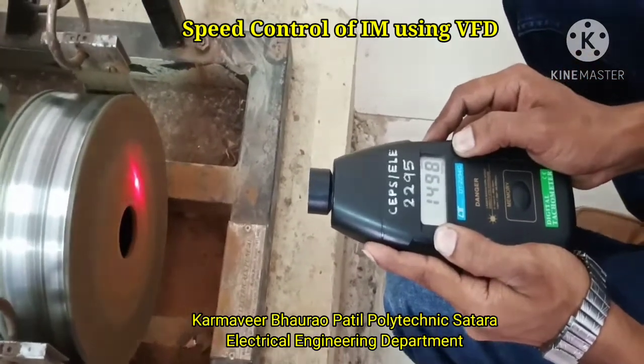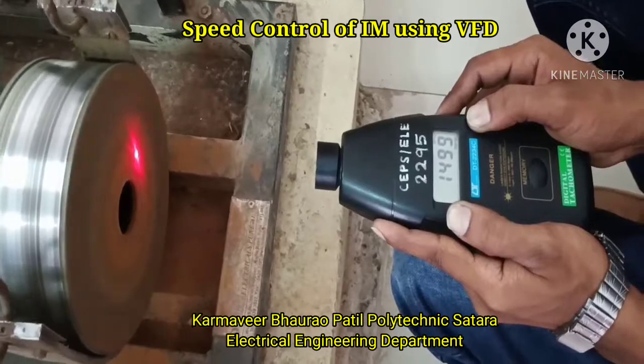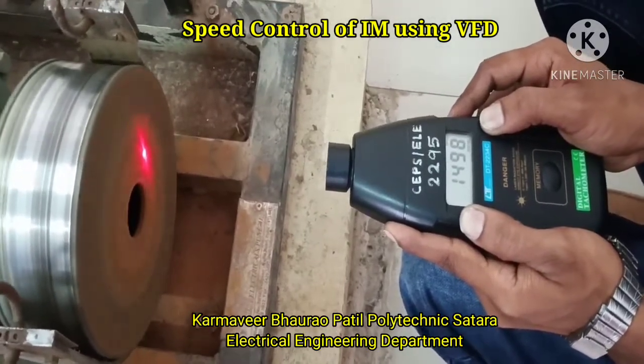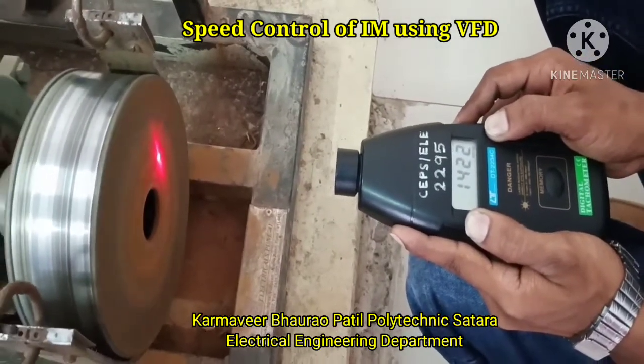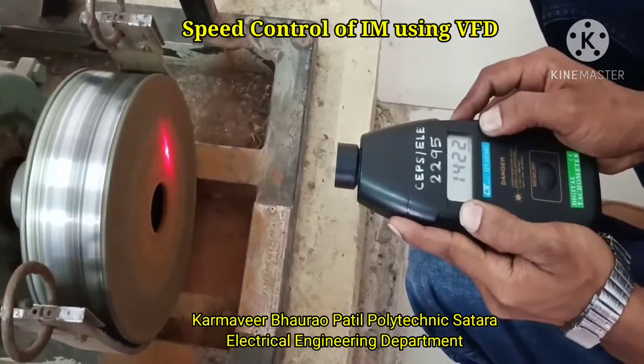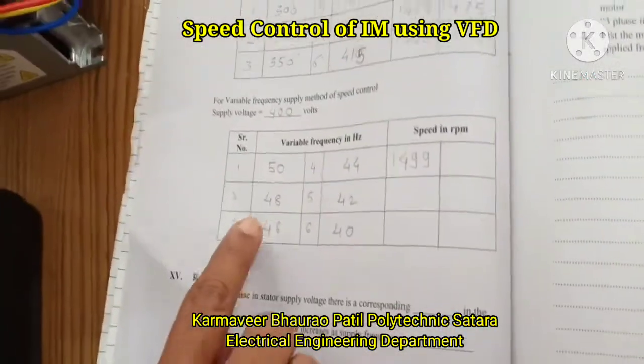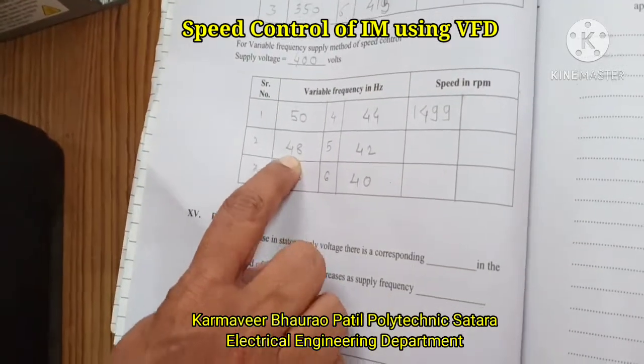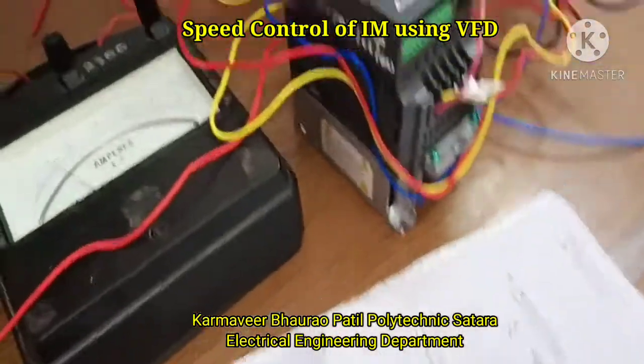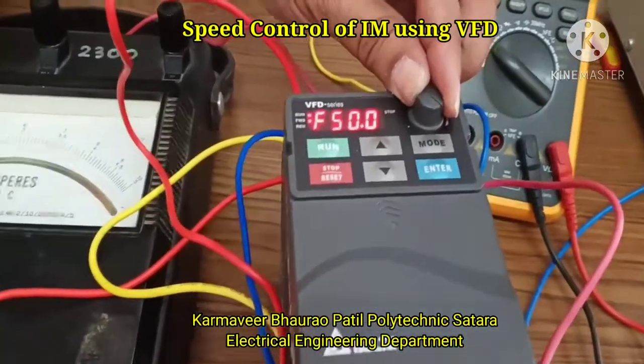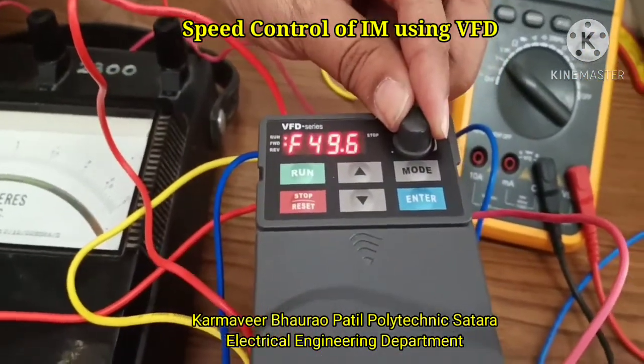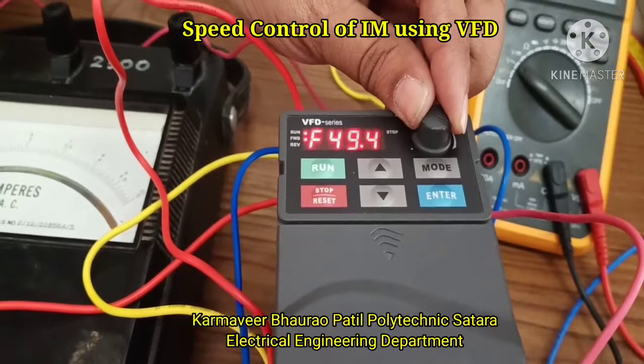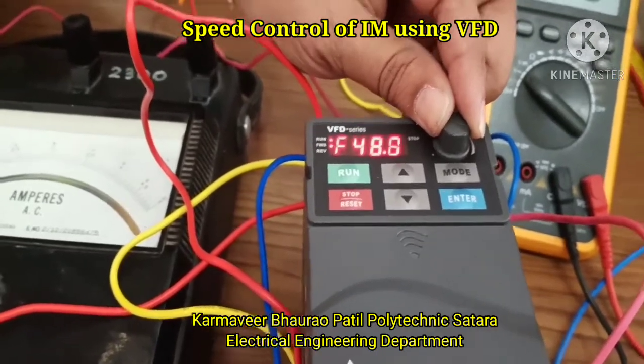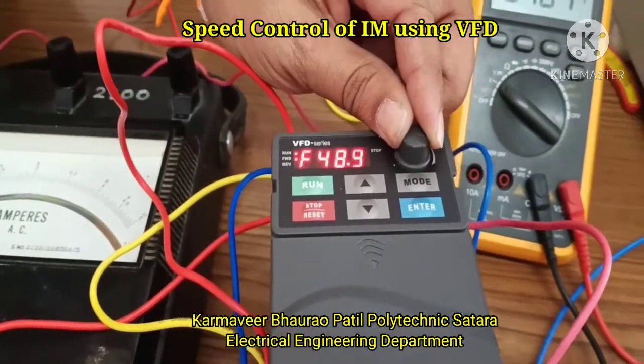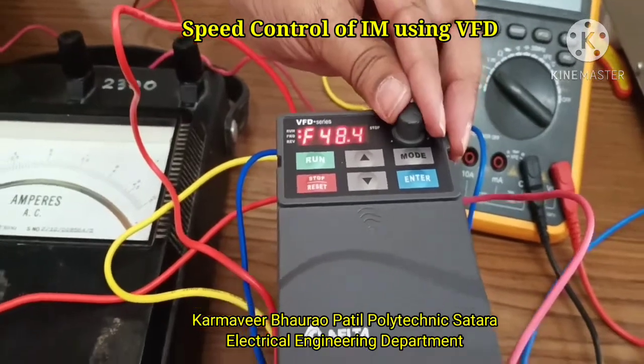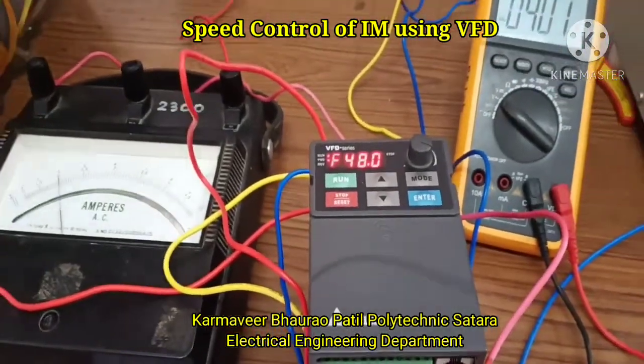How much is the frequency? 50 hertz. And speed is 1499. Next value I want to adjust is 48 hertz. So this is a potentiometer. You will change it, move it slowly, so the frequency will start to decrease. 49.4, like that. I want to adjust the frequency to 48 hertz. So 48 hertz.